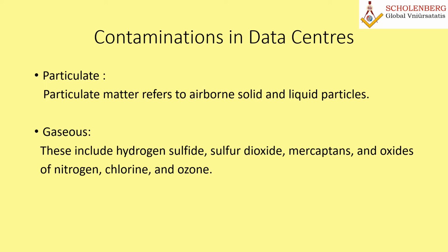The filtration system can be used to mitigate the risk of contaminants in datacom facilities. So while selecting the location for datacom equipment or datacom centers, this particular factor has to be considered: whether your datacom room or building is located in an area where there are industries around, gas, or pollution, as this can affect your data center very badly.